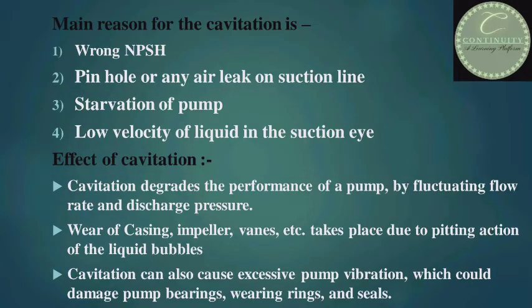There are various causes of cavitation: wrong NPSH, pinhole or any air leak on the suction line, starvation of pump, or low velocity of liquid in the suction eye. Now, the effects of cavitation — cavitation degrades the performance of a pump by fluctuating flow rate and discharge pressure.